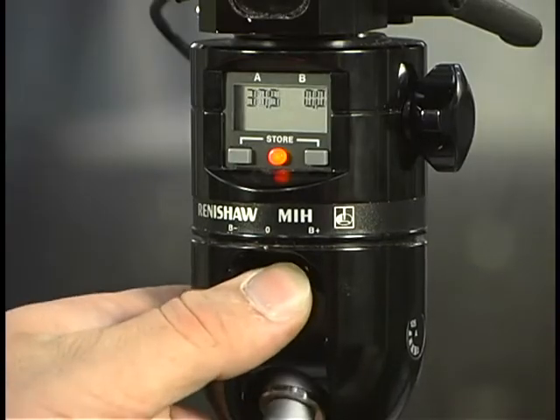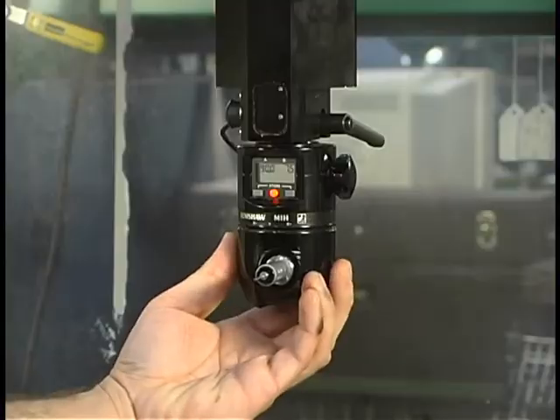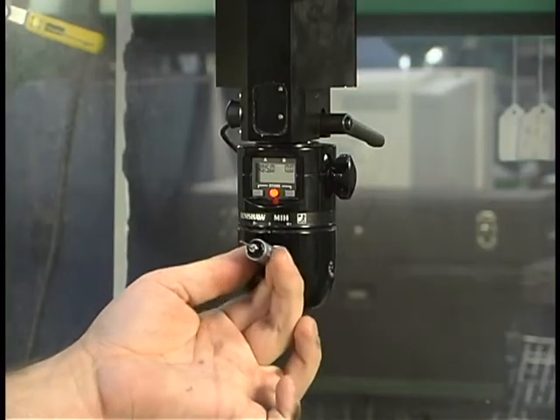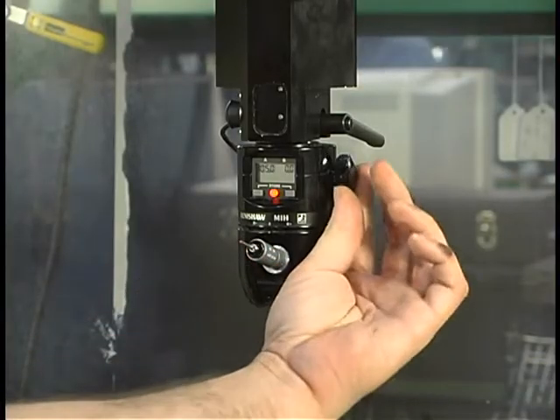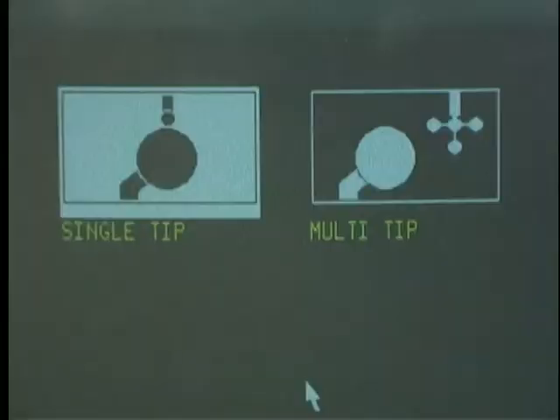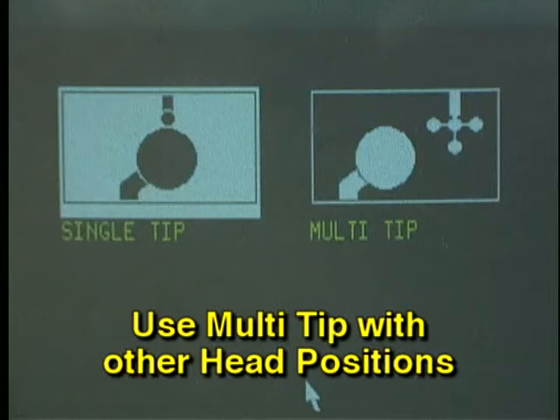Multi tip can be used with indexable head probes. An indexable head can be turned in various angles to allow probing of all the workpiece features. If several probe positions will be necessary during a measurement, the additional head positions can be qualified by selecting the multi tip selection.